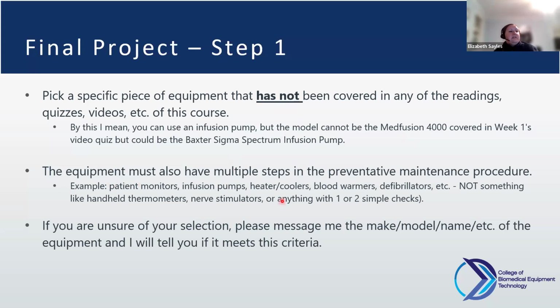The equipment needs to have multiple steps in the preventive maintenance procedure. A device like a thermometer that we went over tonight wouldn't be acceptable, because there's really not a lot of preventive maintenance that we're doing on those devices. But you could do warming and cooling devices. The Blanketrol that we went through has multiple steps. Even the Bair Huggers have multiple steps in the testing part of the procedure, so that would be okay too.